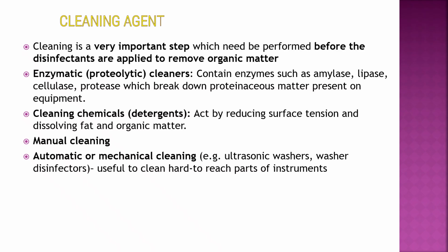Cleaning agent. Cleaning is an important step before disinfectants are applied, to remove organic matter, because few reagents act in the presence of organic matter. Examples are enzymatic cleaners, which contain enzymes like amylase, lipase and protease. Cleaning chemicals are detergents. Methods include manual cleaning and automatic mechanical cleaning, like ultrasonic washers and disinfectors.